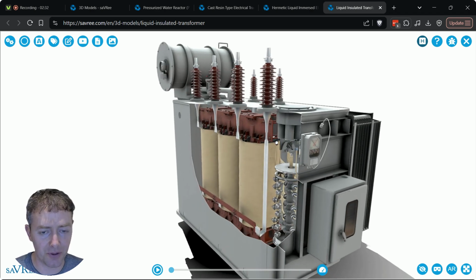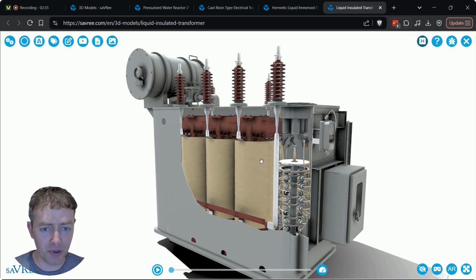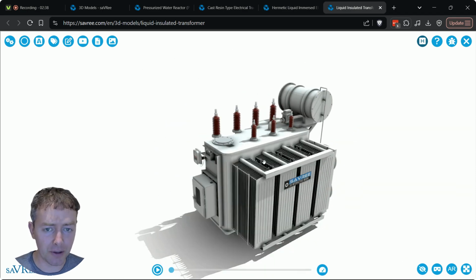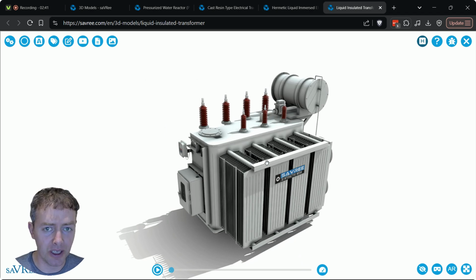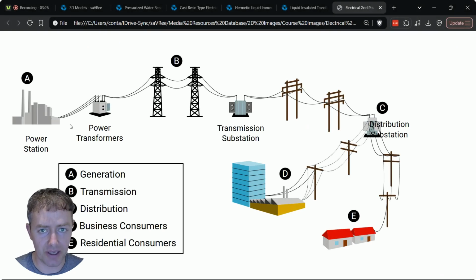Before we have a look at this electrical transformer and look at all of its parts, let's briefly discuss why we might need it. In the power industry, you need electrical transformers to reduce power losses. You get power losses because when you transmit electrical power from a power station, as you can see in this image, here's our power transformer, here's the power station. We're going to increase the voltage, send it into the grid. Then for a transmission transformer, we might increase it again. And then when we get to our distribution substation, we're going to decrease the voltage. So we may have, as an example, 20,000 volts where the power transformer is. Then we go up to 110, then we go up to 220, and then we come back down again, and then we distribute.